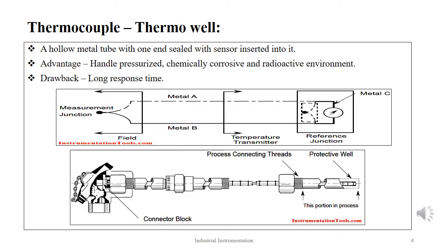In industries, the process environment is not only hot but also pressurized, and there can be corrosive chemicals and substances which are radioactive in nature. Such conditions are capable of damaging the regular temperature sensors. Therefore, the thermocouples are modified into thermowells, which are basically hollow metal tubes having one end open and the other end sealed. The thermocouple sensor is inserted inside this hollow tube, which is then introduced in the process environment. The main advantage of the thermowell is that it can handle pressurized, chemical, corrosive, and radioactive environments, but at the cost of slow measurement response.